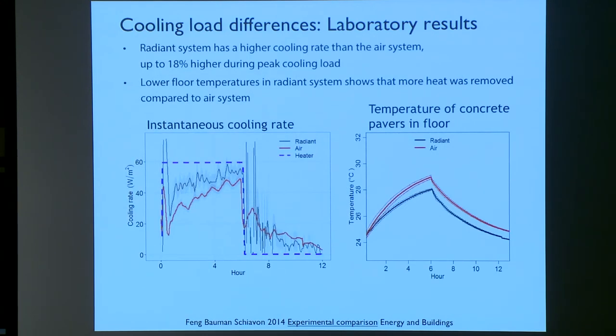This is an example of some of the results that came out of this. What we found is that the radiant system was able to remove a much higher rate of energy, or a higher cooling rate, than the air system - up to 18% higher during peak conditions. That was indicated both by the calculations of the cooling rates, by looking at the delta T of the air or water and the flow rates, and also by measuring the temperature of the slab. The lower temperatures of the floor slab in the radiant systems indicated that more heat was being removed by the radiant ceiling.